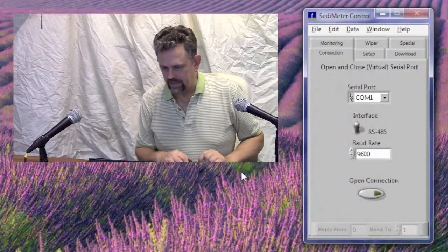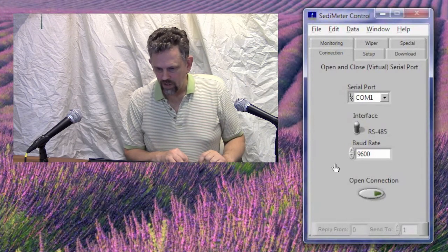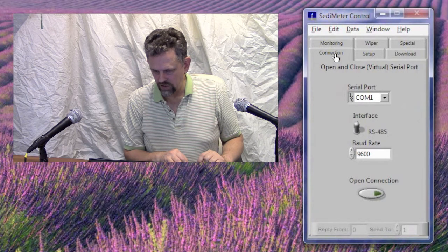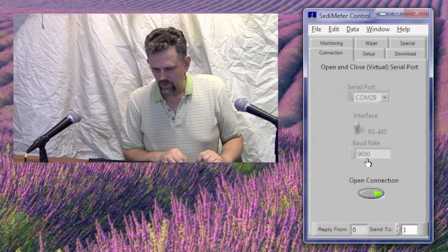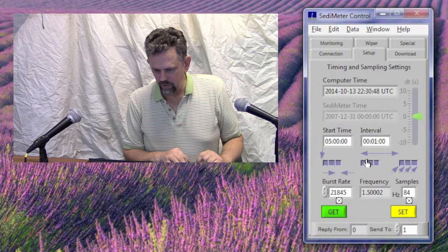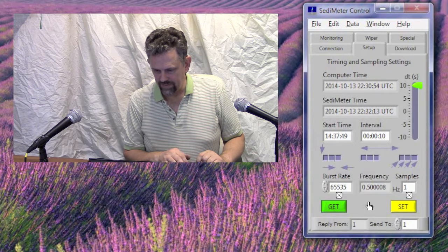Let's set up the computer software. Let's connect to it from the computer. We open the SediMeter application and in the connection tab we select the port. In this case it's COM29 and we click open connection. Then we go to the setup tab and here we can click Get to find out what the time is in the sedimetre. Now the time is a little bit wrong, so we click Set and set it to the same time as in the computer. If we want to check it, we click Get again and now the time difference is zero.